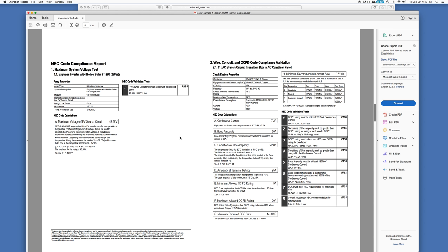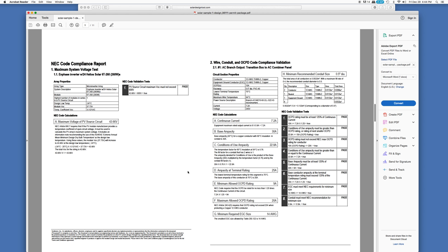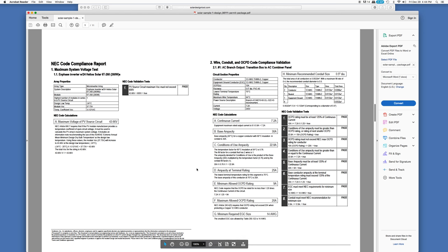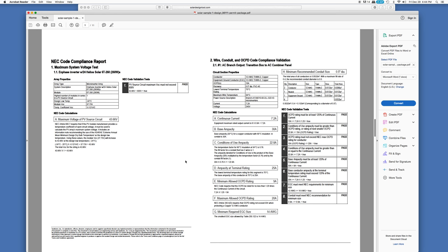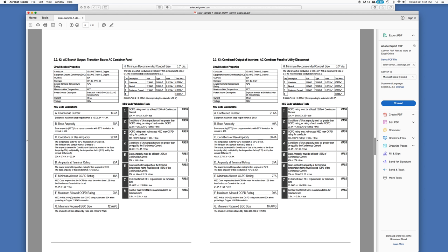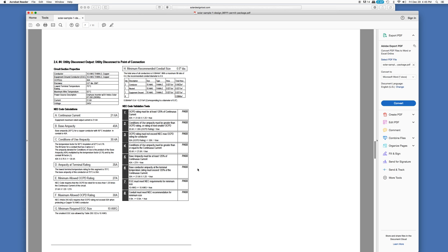Here's some of the information in terms of, again, current, ampacity, all this information. This was all done automatically through the software. This is all stuff that normally you would have to do manually, by hand, do the math, figure it out, you know, figure out, you know, what size wires you're going to need, all that. And again, I highly recommend that you do take a solar design class if you want to design your own solar system. I did. It was great. It's very good knowledge. But again, here using the solardesigntool.com software, it does all the math for you. So it's pretty cool. And also it's good as a double check, you know, go through, design it manually, come through, use the software, use the software as a check to make sure that you did your work correctly. Again, it's just the information on the branch circuits, the combined output, all of that. Utility disconnect information. A lot of this in here, there's some rules of thumb, you know, continuous current, some other things like that. Make sure you're using the right size wiring, right current ratings for things.